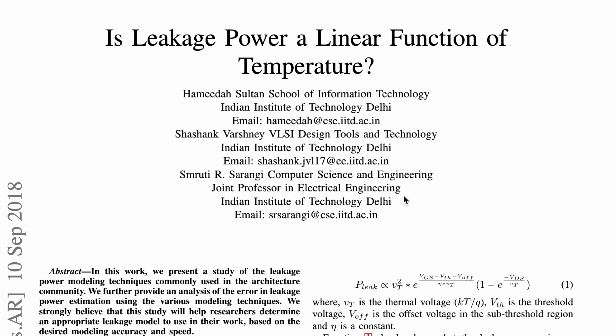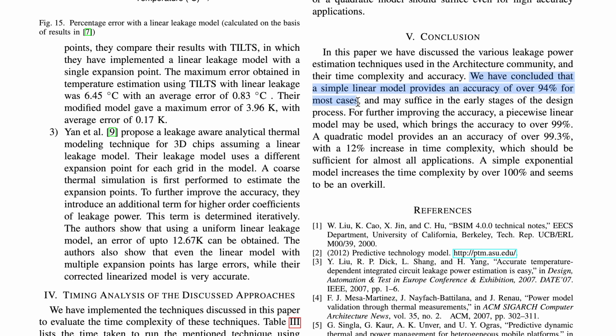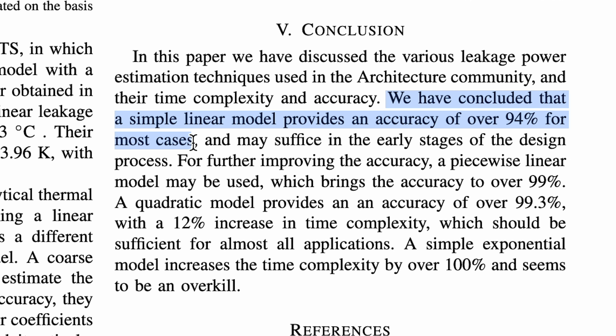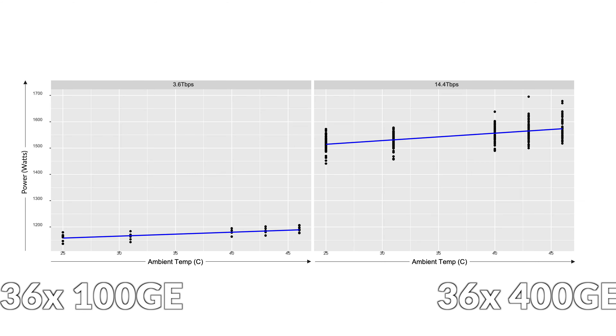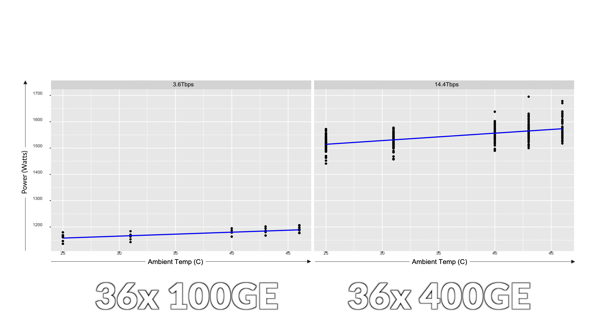Leakage power is almost linearly increasing based on temperature. Take a look at this line card configured with 36 ports — 100GE on the left and 400GE on the right. They are not doing anything, yet the power used is regularly increasing when the ambient temperature goes up.